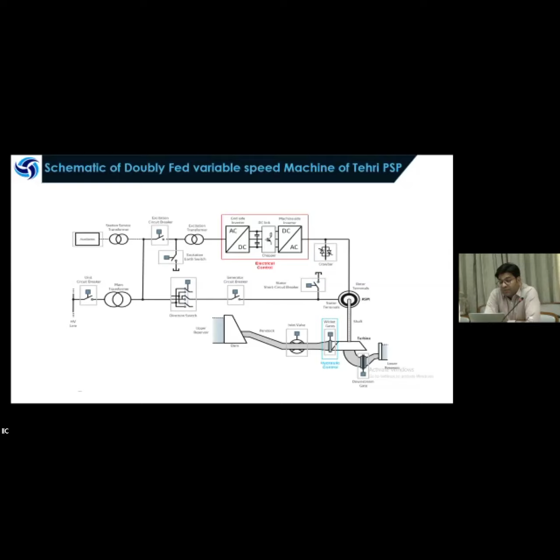And this is the basic principle of the variable speed, because this variable speed asynchronous machine never operates at the synchronous speed. It will operate either at subsynchronous speed or supersynchronous speed, meaning higher or lower than the synchronous speed. When this machine is operated at the subsynchronous speed, then the total mechanical output power equals the stator power. The rotor will draw the power from the grid.